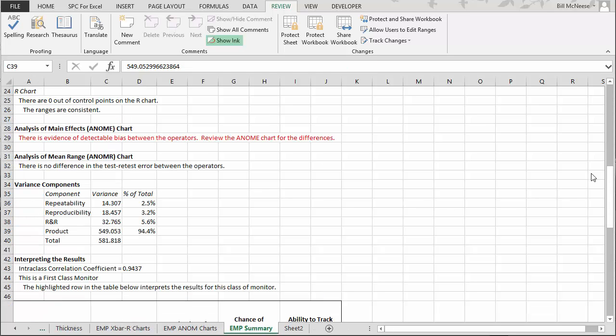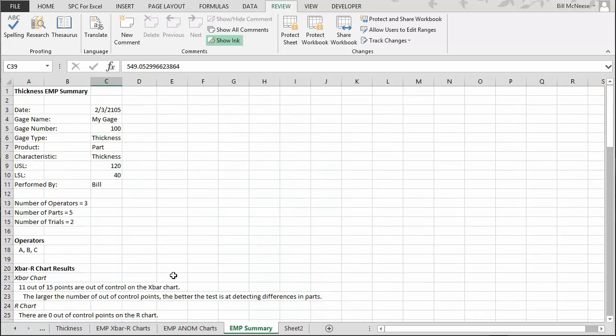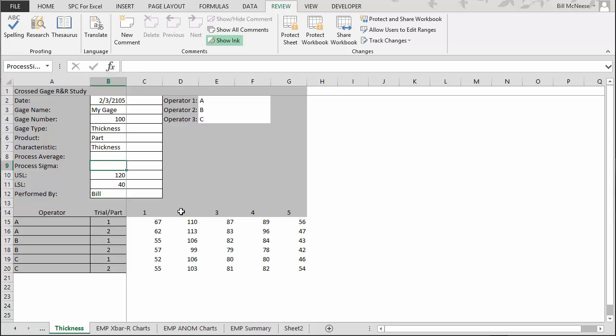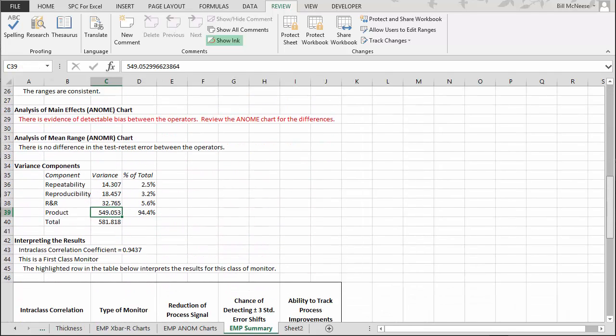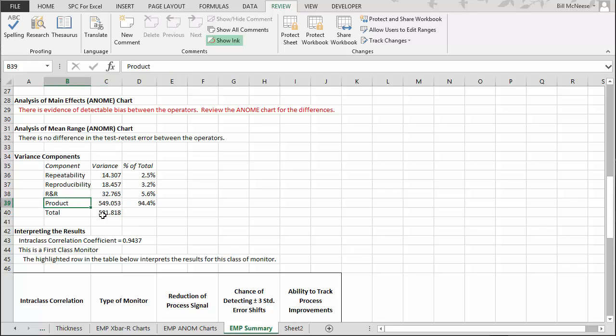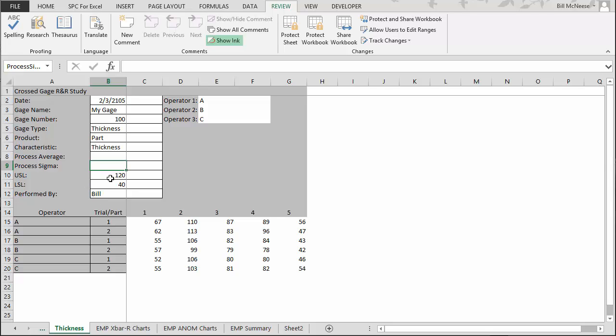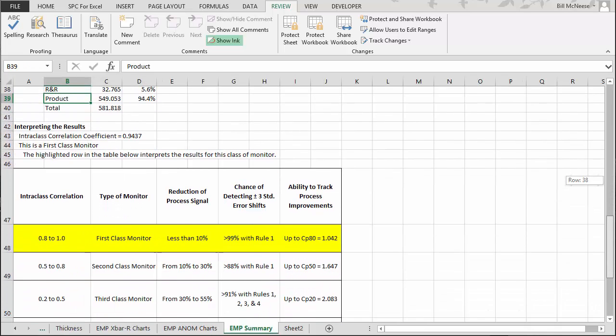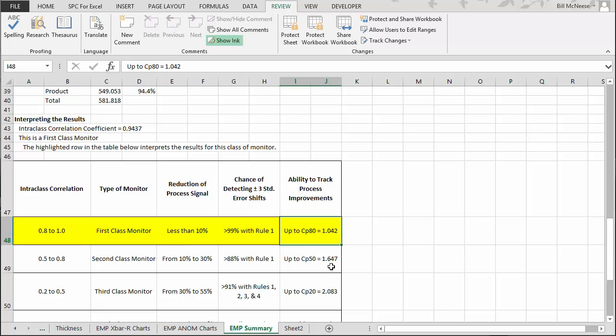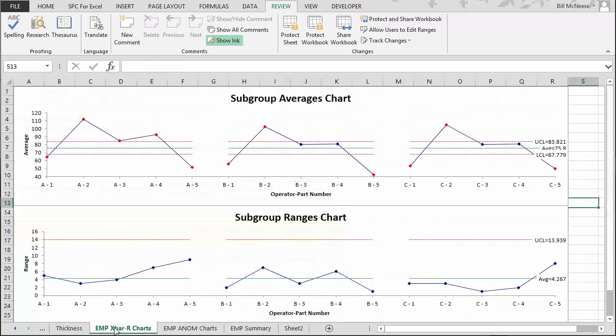A couple additional notes: if you enter a value for process sigma — for example, from a range chart kept on your product in production — the program will use that in place of the total variance and calculate the product variance from that estimate, which helps if your selected parts aren't representative of the process. Also, if you have one-sided specifications and include the average, the program will use Cpk instead of Cp when calculating the ability to track process improvements. This is how the software analyzes a gauge R&R study using the Evaluating the Measurement Process methodology. Thanks for watching.